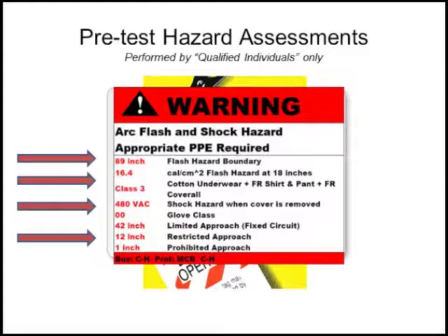Now that we've talked about having the proper quality of meter, in other words, a Cat 2, Cat 3, or Cat 4, we need to start doing our hazard assessment. Is there a risk of shock or arc flash? Now, the best resource for this is going to be NFPA 70E, and we like to use the latest edition. If your workplace has already had the hazard assessment, then we should be posting that information on the equipment.